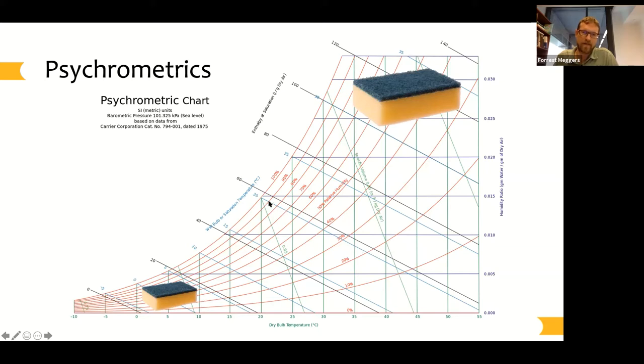These are the lines you follow if you don't heat or cool the air but just let water evaporate into it. So if I start down here in Arizona at 40 degrees and about 20% humidity, and just release water vapor into the air without adding or removing heat, I move up this black line, which is a constant enthalpy, or constant energy, line — and I can cool the air down to 20 degrees just by increasing its humidity up to 100%.